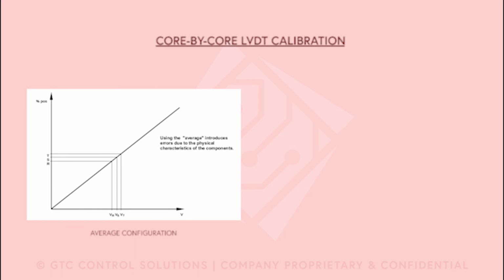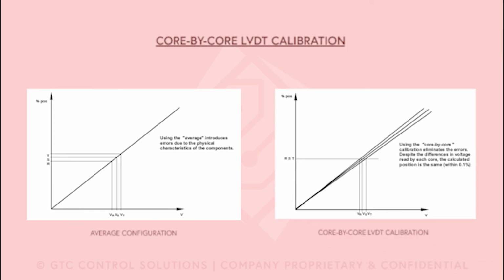When you do the core by core calibration, this is what you're doing. And it's obviously different. The voltage interpreted by each core is converted by its own gain and its own offset into the same position for all three cores. And it's amazing the difference. The position interpreted by each core is almost exactly the same, with a 0.1% difference between cores.